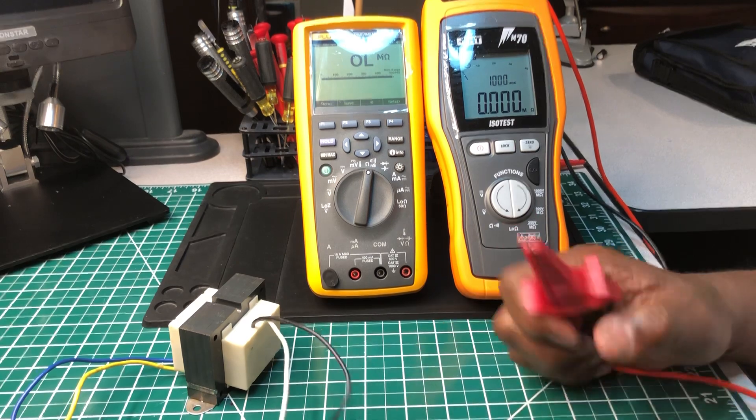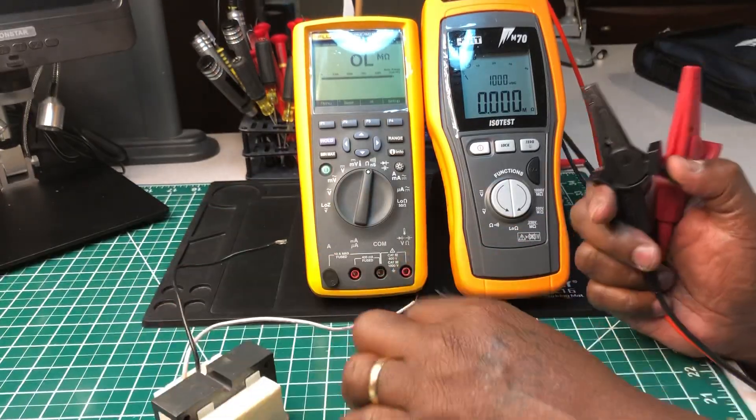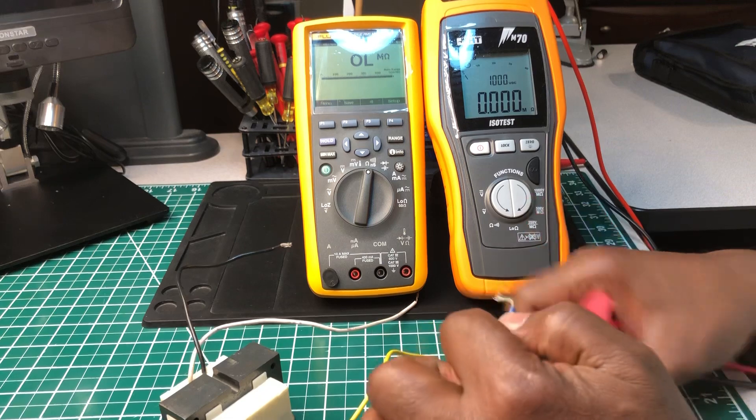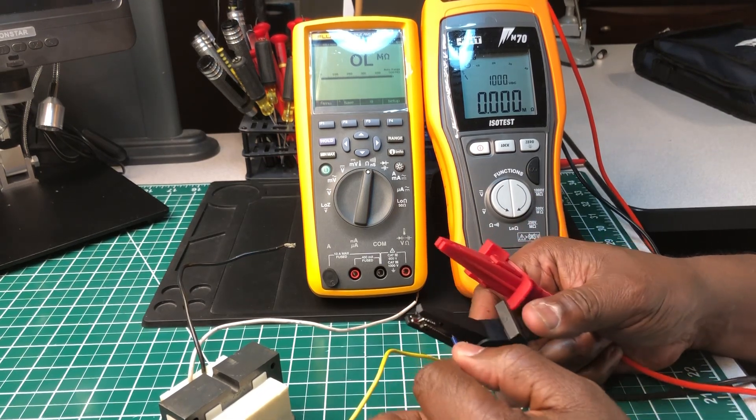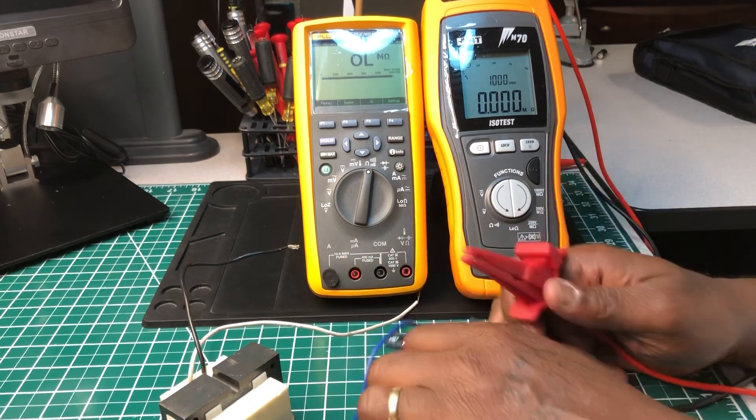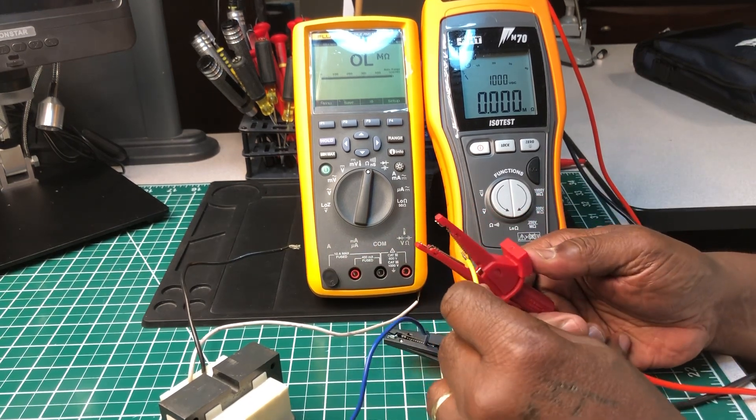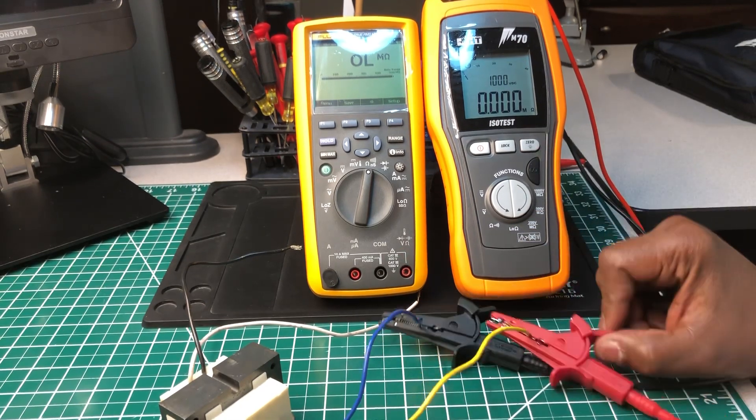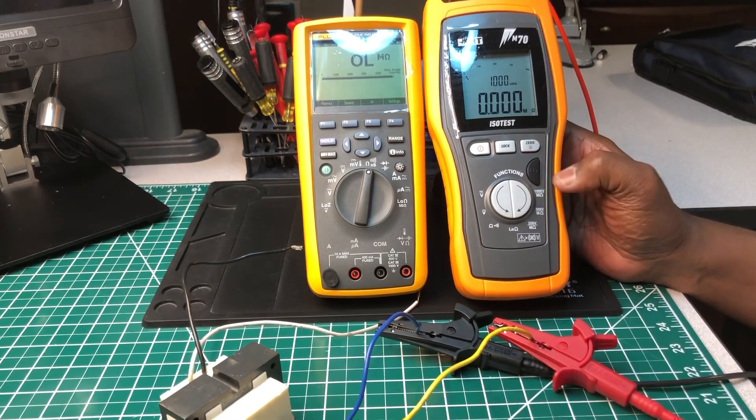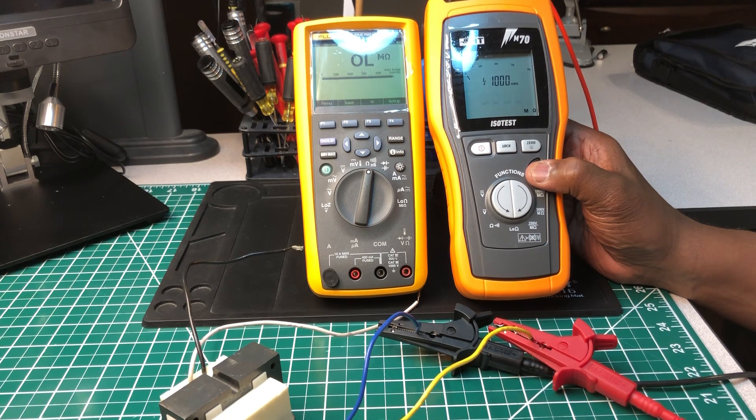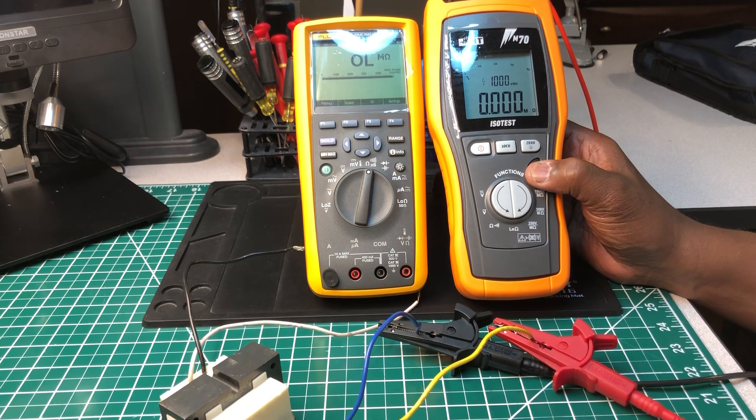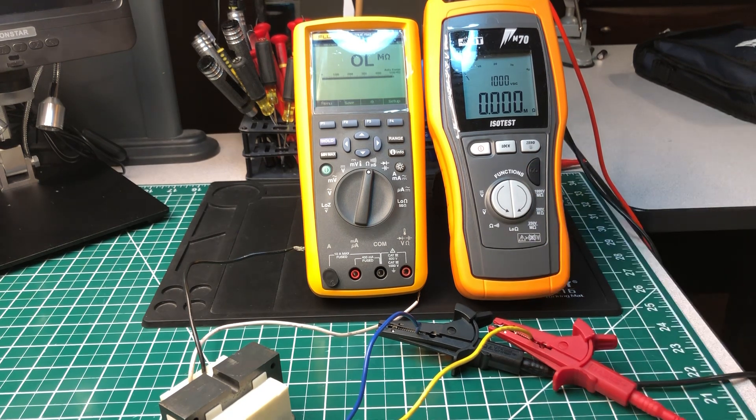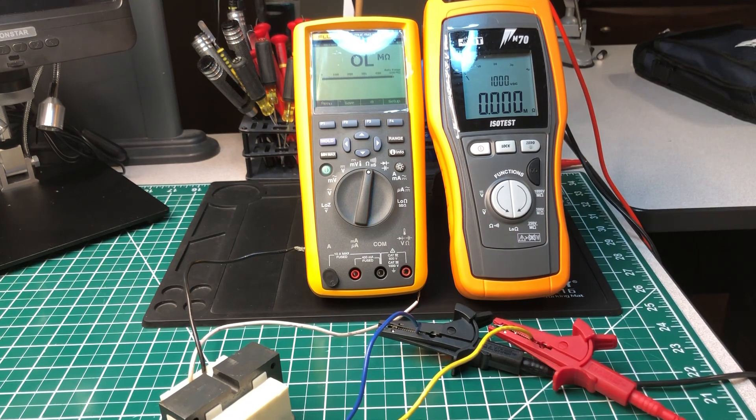At a thousand volts there's no resistance, so I know it's good now. If it could handle a thousand volts DC and there's no resistance in these little wires in the transformer, it has to be good. Let's try the primary side at a thousand volts also.